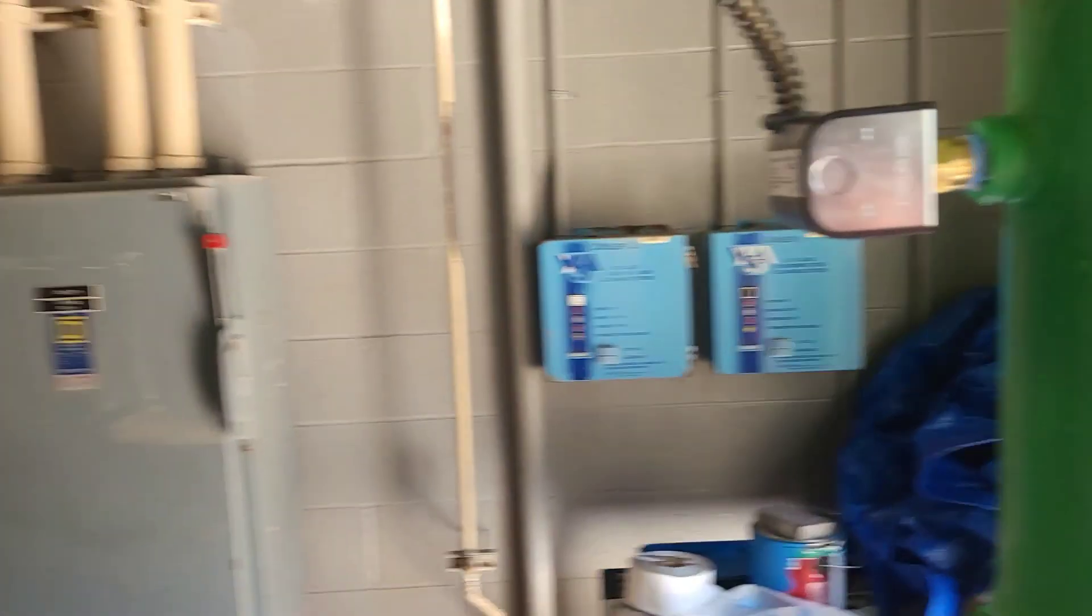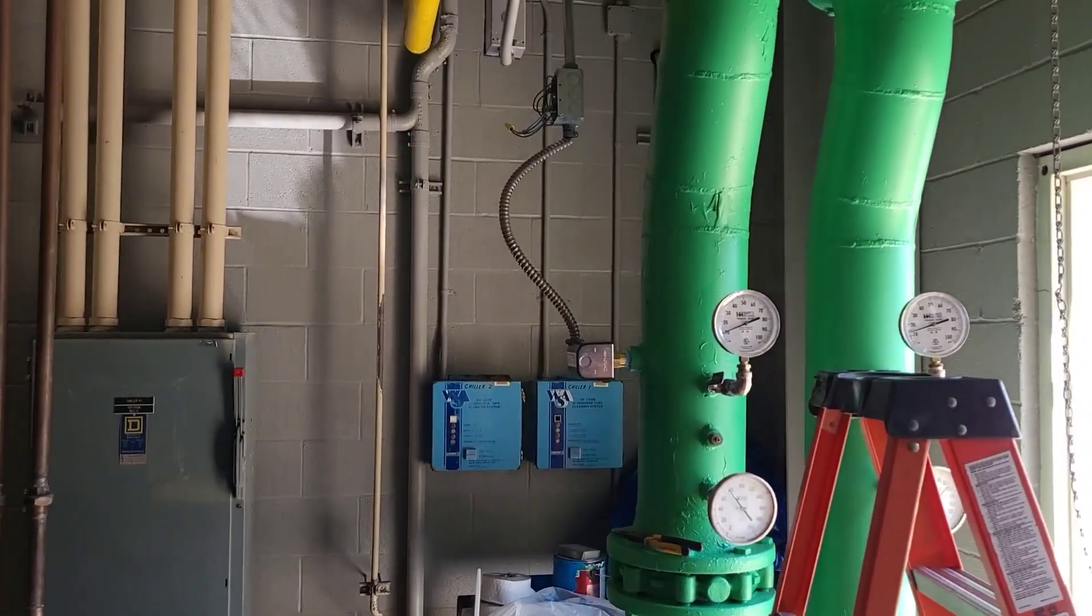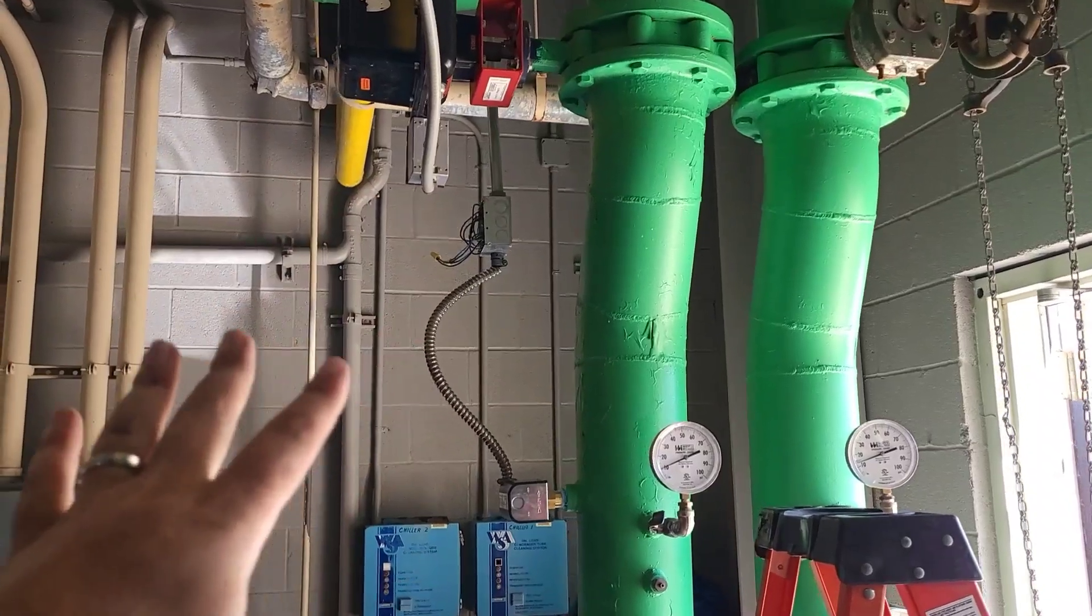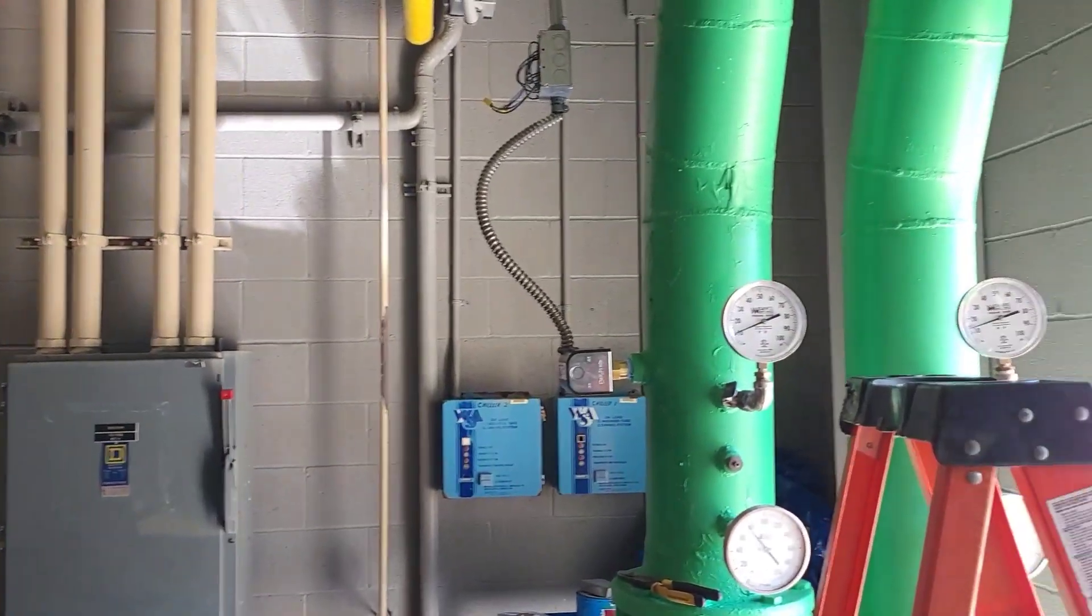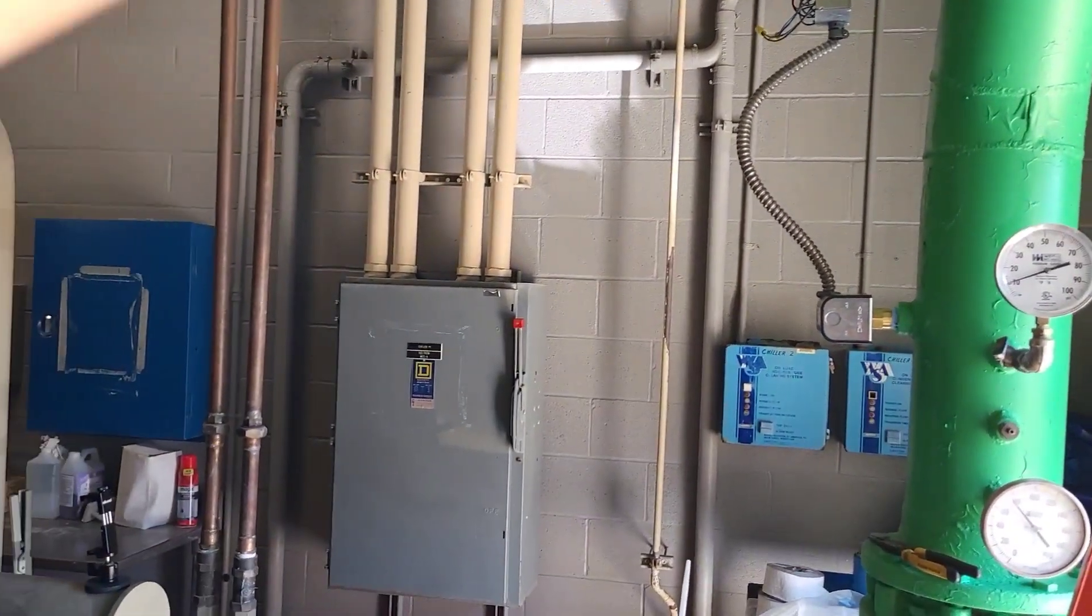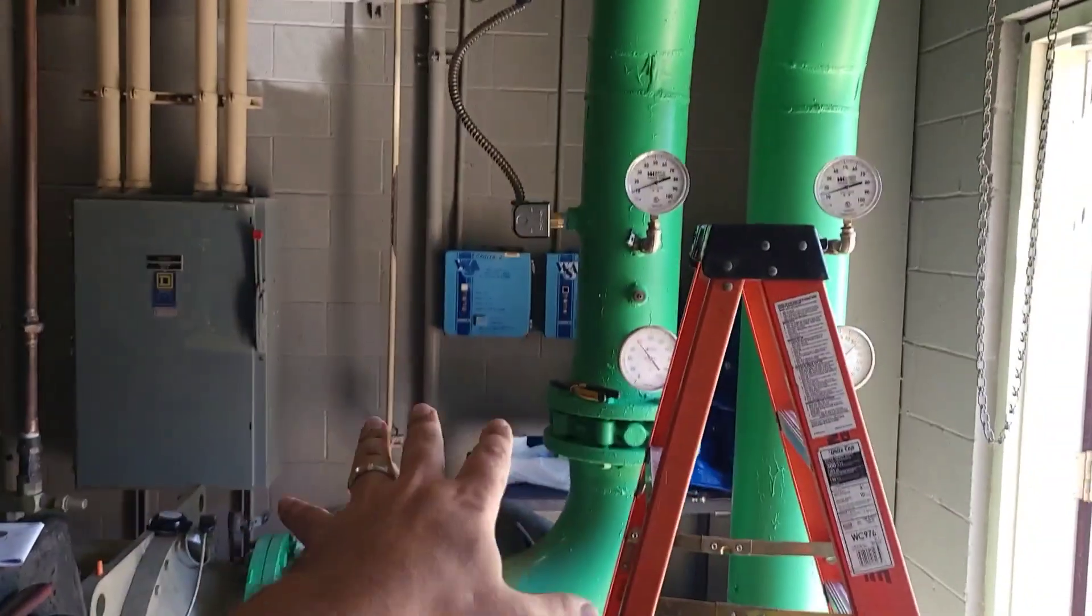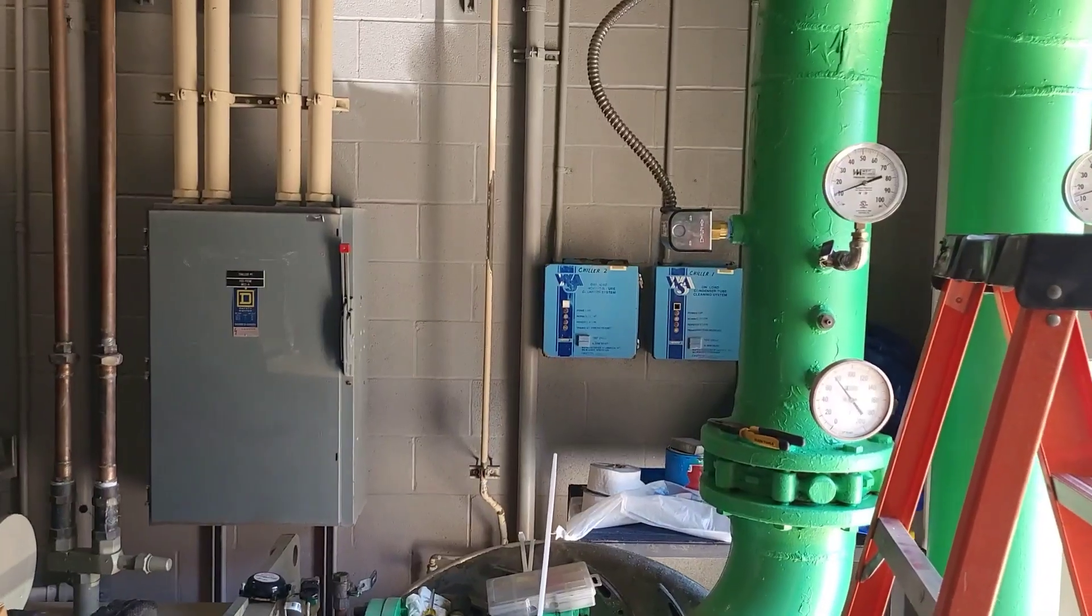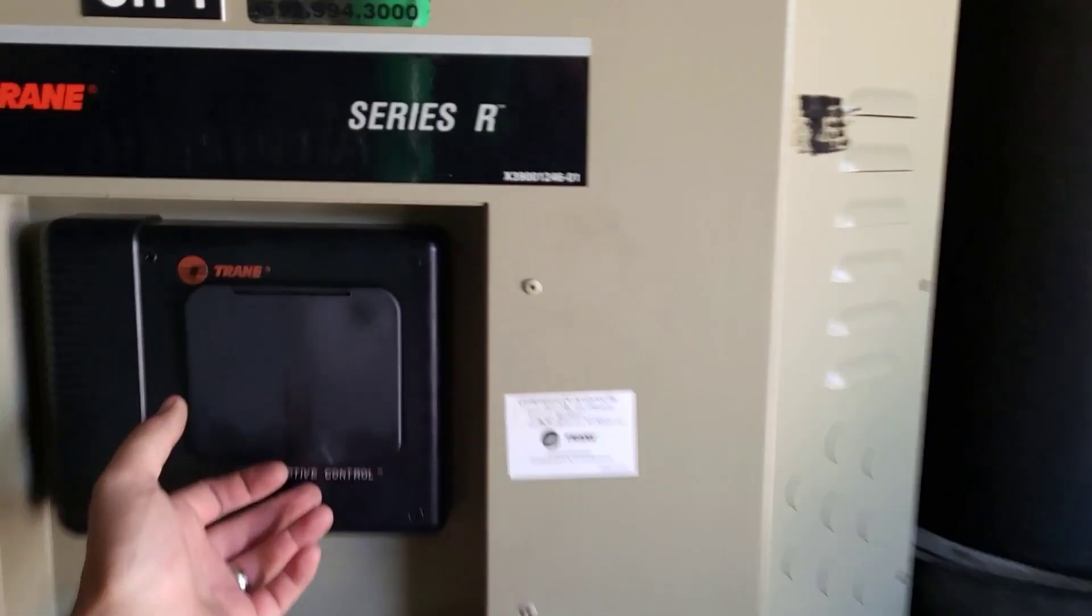New flow switch is installed. Got the pump back online. Now one of the things you're going to notice is I didn't take a whole bunch of time trying to worry about bleeding any air or anything out. The reason for that is above us are the towers. They are open loop, so all the air is going to get pushed up there as soon as I turn the pump back on. It's just going to push through the incoming back out, and all the air is going to get forced up into the tower. All the tower makeup is done at the tower for the condenser water. So it wasn't super critical. If this was a closed loop system, I would have had to have been way more conscious about how I got that air back out of the loop and then all the air bleeders and such actually did their job.